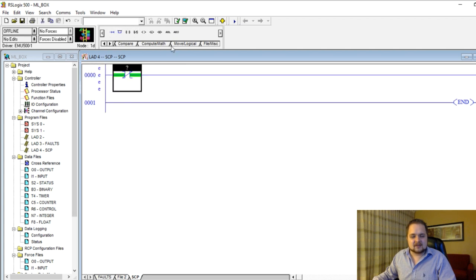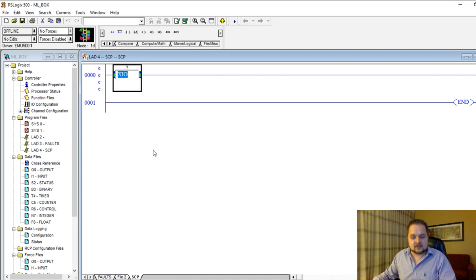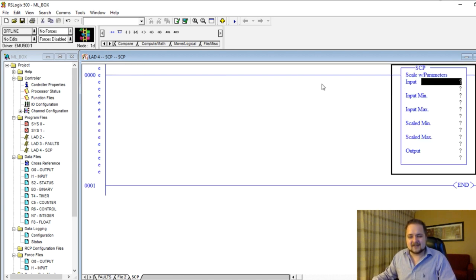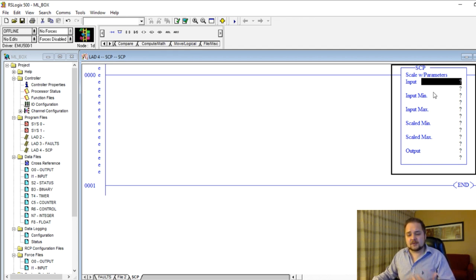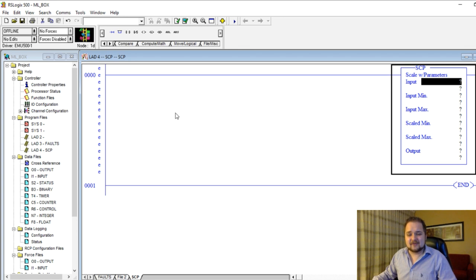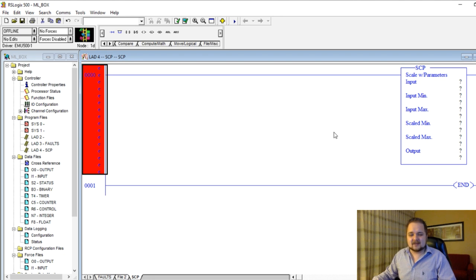So from the main we're going to do routine three, then routine four, and we're going to start by creating our instruction. There's many different ways you can find the instruction, but I prefer to just copy anything in and then just change instruction type, SCP. And as you can see, it is called scale with parameters. So there's going to be an input, which like I said is typically an analog input, but of course here we're just going to simulate a certain value which we're going to type in. Then we're going to have input min, input max, scaled min, scaled max, and the output.